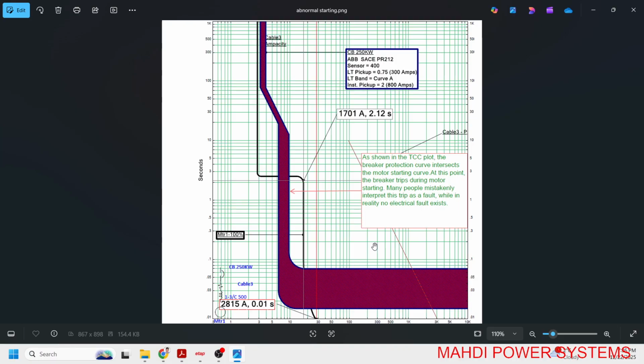Here motor starting enters the breaker protection curves. What happens here? When the motor is started, the operator pushes start, and the breaker immediately trips, but not because of a fault condition. Because of the TCC, the curve of the breaker enters the curve of the motors. That's why the breaker immediately trips. Tripping immediately has two reasons. One is this concept, that the breaker setting intersects the TCC of the motors, and the second reason is a fault.